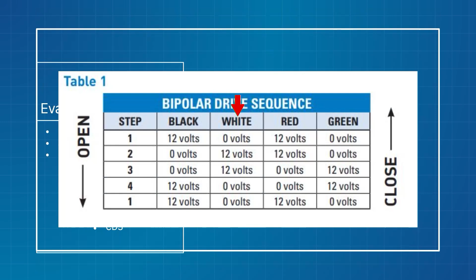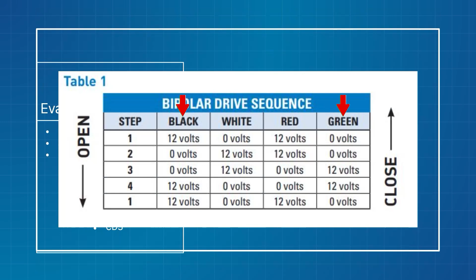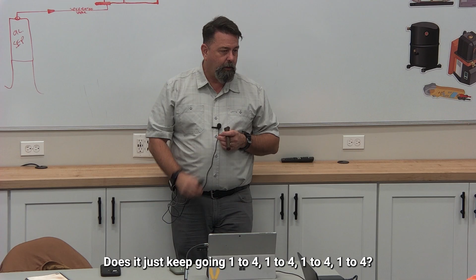My controller is telling this valve to open, then it's going to cycle through, sending power on black and red very quickly, then white to red, then white to green, then black to green very quickly. That's going to tell it to open. To reverse and close, it will work from 4 to 1 instead of 1 to 4.